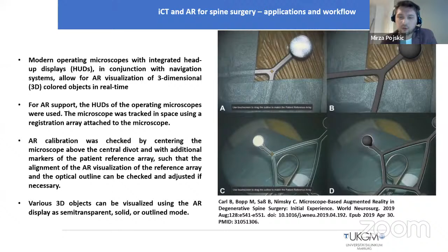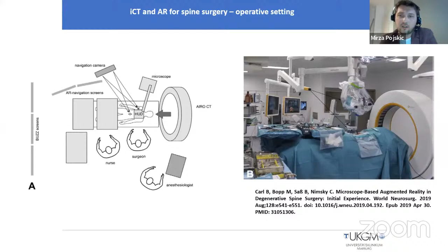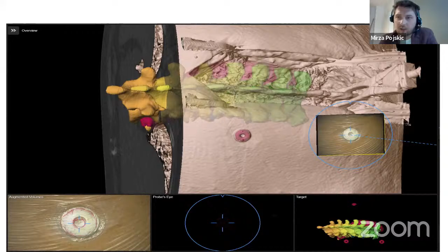This would be our intraoperative setting. Here you see a patient who is undergoing a spine surgery in a prone position with a reference array which is attached on the spinous process. And you see over there the registration camera, which is then pointing at the reference array on the patient and at the reference array on the intraoperative microscope. How to check the accuracy of augmented reality and the accuracy of the microscope? Well, we usually put fiducials around the skin incision, and you can center the zoom or the focus of the microscope on the fiducial and then check on the display if you are exactly at that projected position.